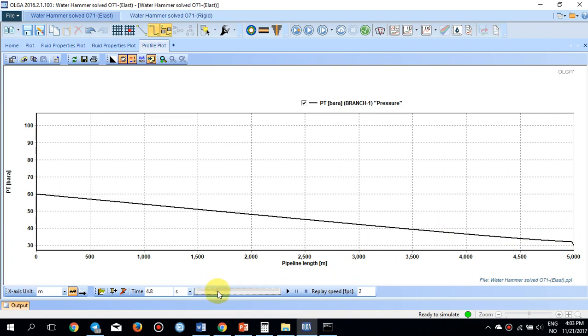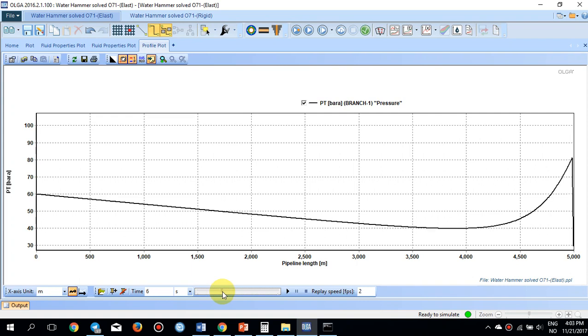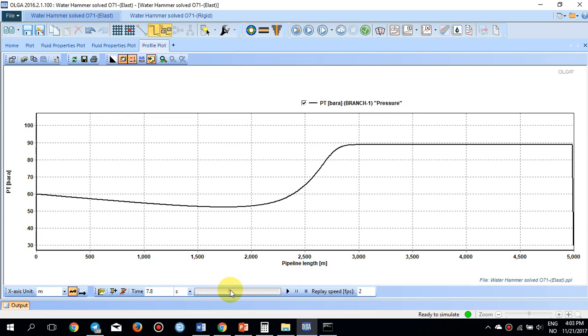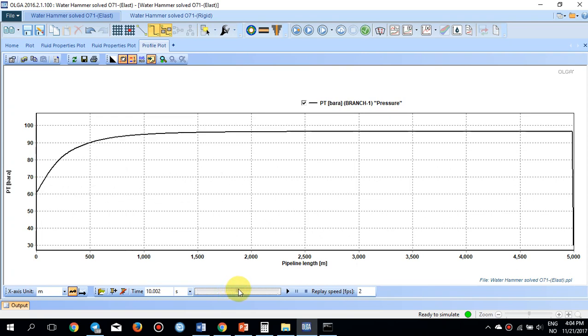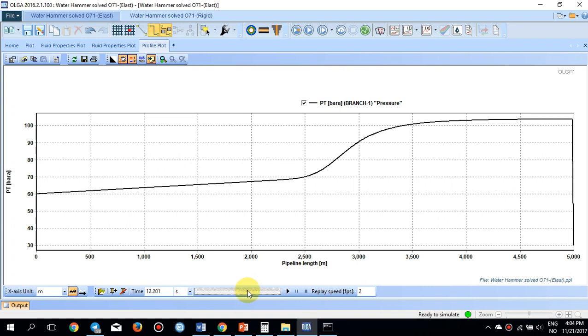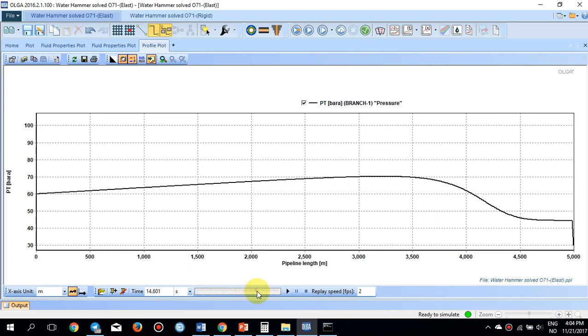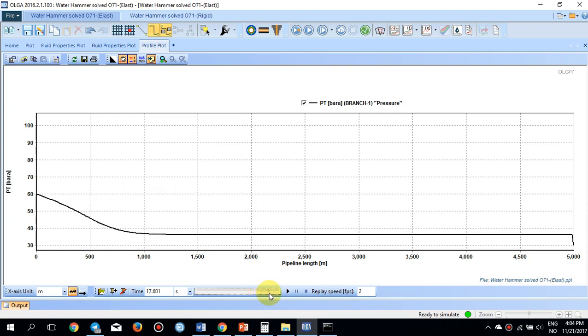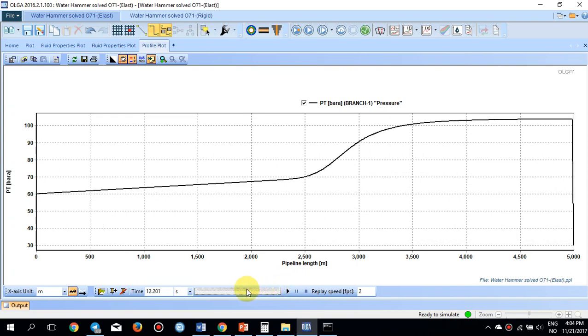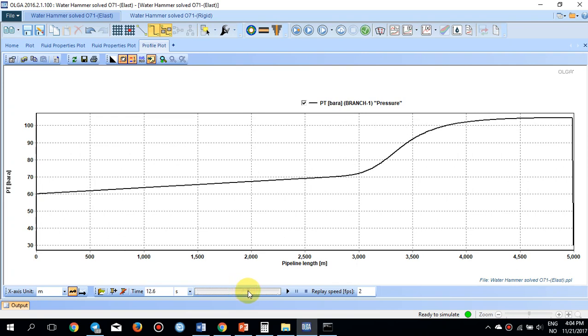As the valve closes further, a clear pressure peak is visible at time T equals 6. As time progresses further, the pressure wave propagates along the pipe and pressure builds up. By around T equals 10 seconds, the pressure wave is traveling back, and the wave amplitude is diminishing — likely due to the elasticity of the wall dampening the pressure wave.